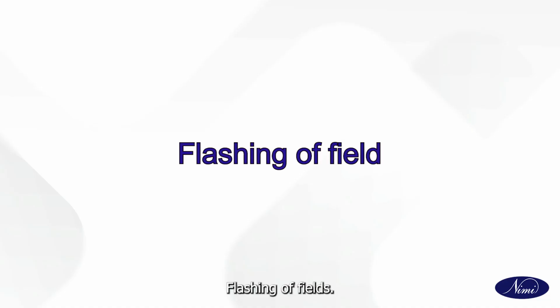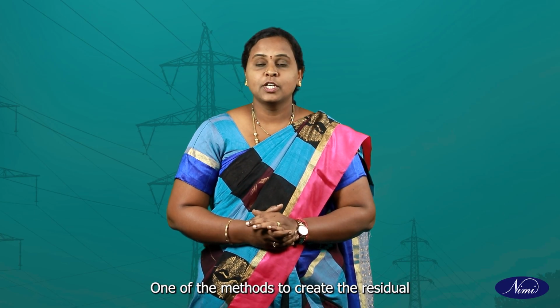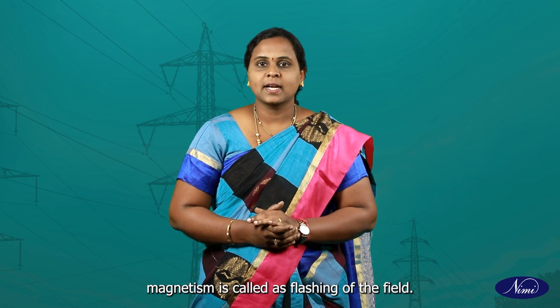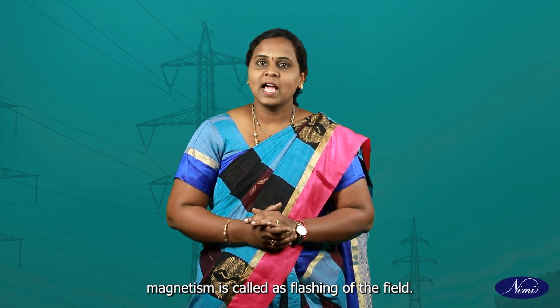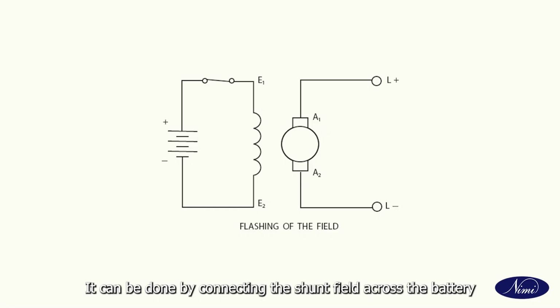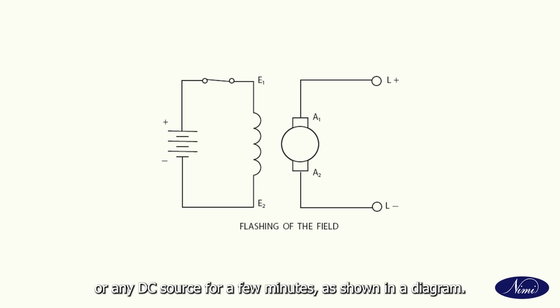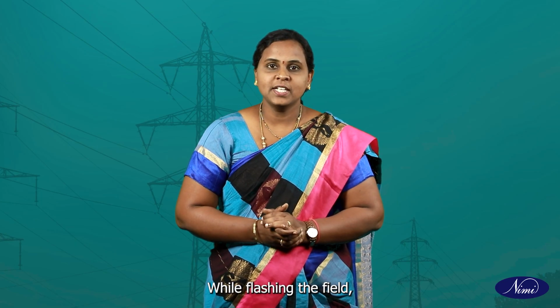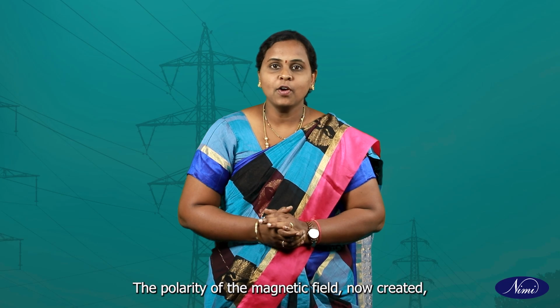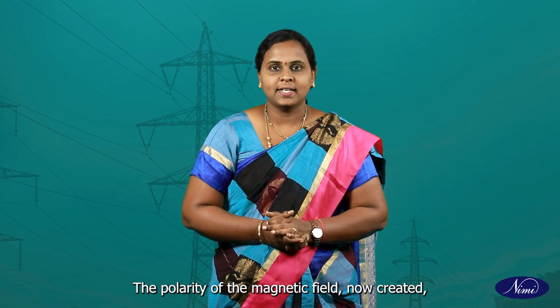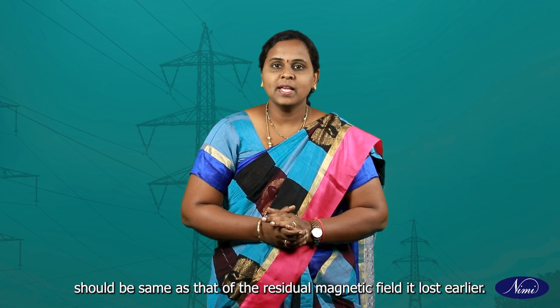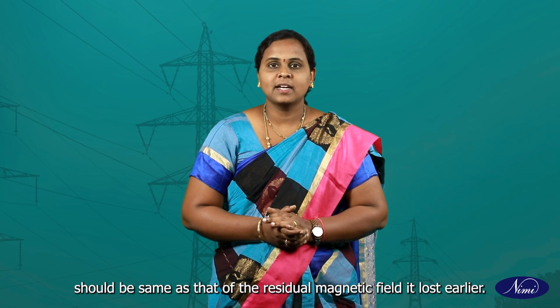Flashing of fields. One of the methods to create the residual magnetism is called flashing of the field. It can be done by connecting the shunt field across a battery or any DC source for a few minutes, as shown in the diagram. While flashing the field, the polarity of the magnetic field now created should be the same as that of the residual magnetic field it lost earlier.